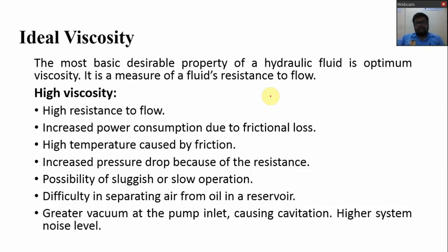So it will increase the power consumption, and due to this extra power it will also generate extra heat. A higher viscosity has a higher resistance to flow. These are the characteristics: increased power consumption due to friction loss, because flow of the fluid is very difficult, and high temperature caused by the friction, which is also a concern in high viscosity.